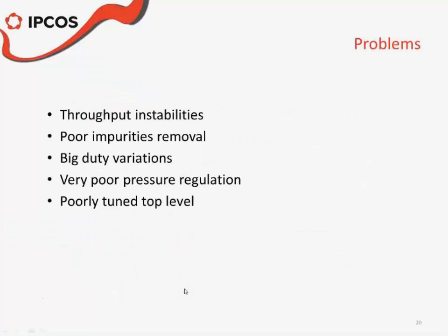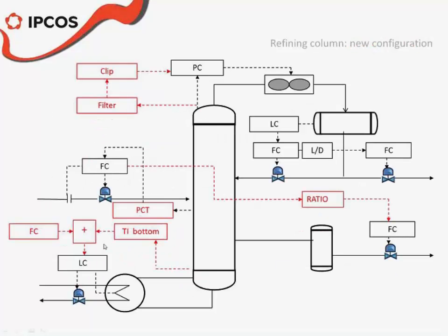And if you remember, we were talking about big duty variations. Those duty variations were mainly due to pretty much uncontrollability of the level in the reboiler.